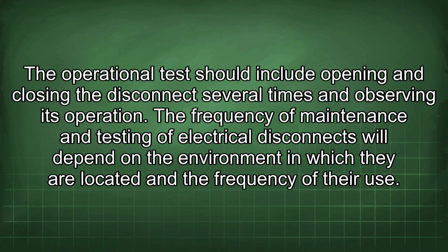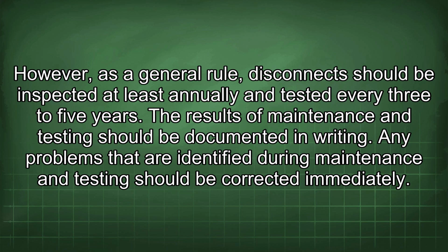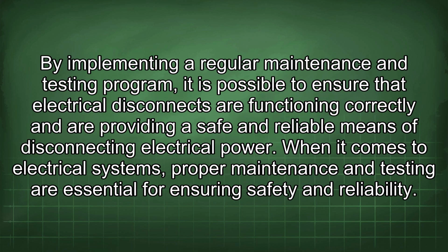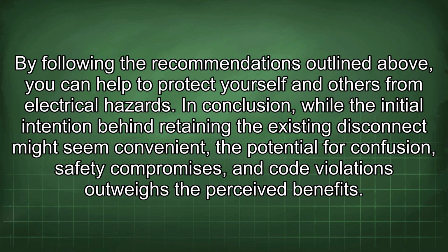The frequency of maintenance and testing of electrical disconnects will depend on the environment in which they are located and the frequency of their use. However, as a general rule, disconnects should be inspected at least annually and tested every 3 to 5 years. The results of maintenance and testing should be documented in writing. Any problems that are identified during maintenance and testing should be corrected immediately. By implementing a regular maintenance and testing program, it is possible to ensure that electrical disconnects are functioning correctly and are providing a safe and reliable means of disconnecting electrical power. When it comes to electrical systems, proper maintenance and testing are essential for ensuring safety and reliability. By following the recommendations outlined above, you can help to protect yourself and others from electrical hazards.